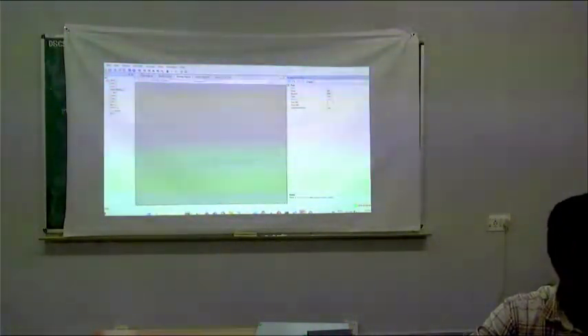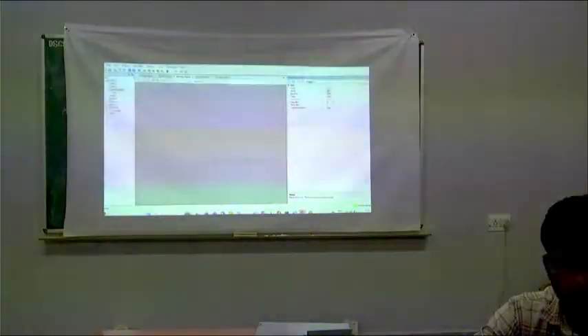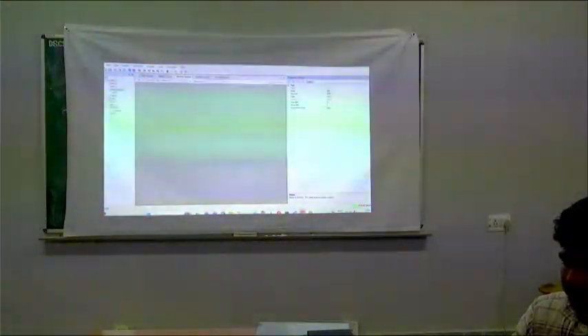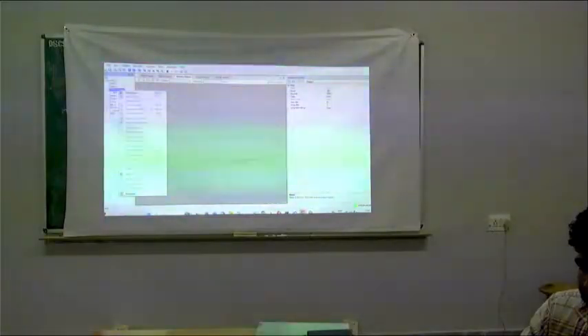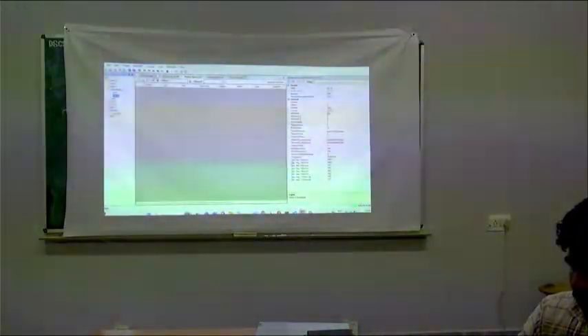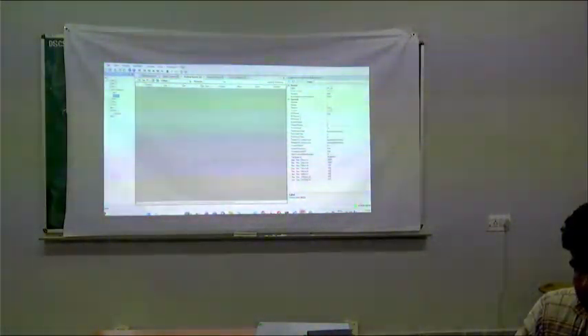Okay, so here we specify the configuration for that port. We have defined the baud rate, the parity, all those things, and then you add a device. You go there and select one, add one device there. Here you go to the COM3 port, click on add. So you can add multiple meters like that. Okay, I can add a device and we can add multiple meters to that, and for that I will define an address. If you see there, the address field is vacant. I can give the address that I would have set for this meter. Then once I apply this, it will search for that meter with that specified baud rate and it will start communicating.